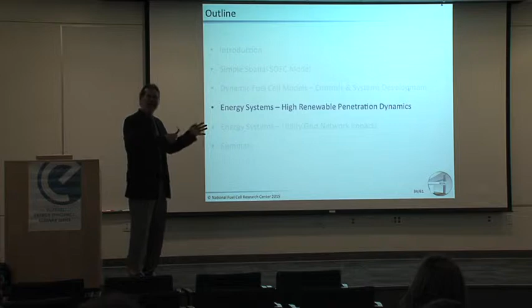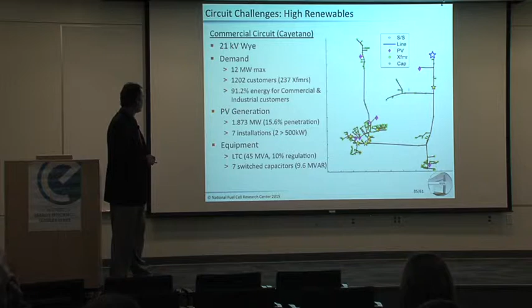We've studied some of these circuits in real electric utility grid networks. This one happens to be in PG&E service territory. This is the substation, and it has all these transformers you see in green, and all these starred locations where there are significant solar installations. In this case, almost 1.9 megawatts of solar power is installed for a circuit that has a 12 megawatt maximum power delivery. So about 16% of the power on average is met by the photovoltaic systems on this grid.